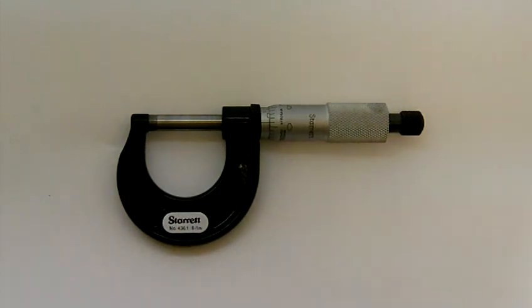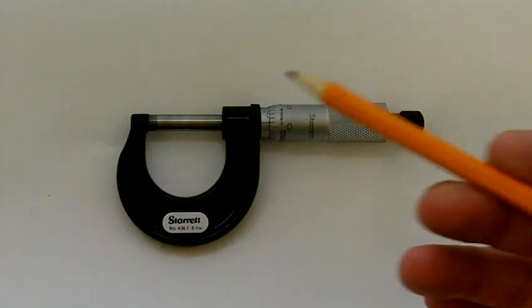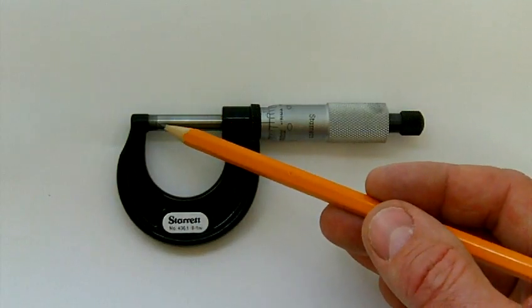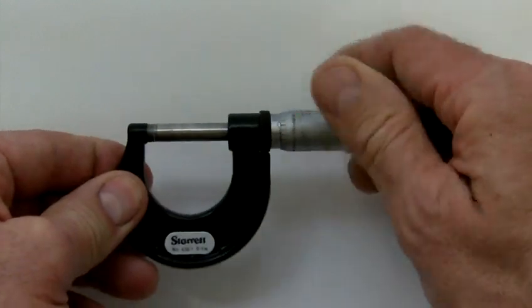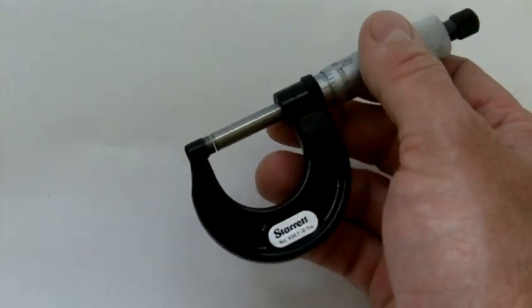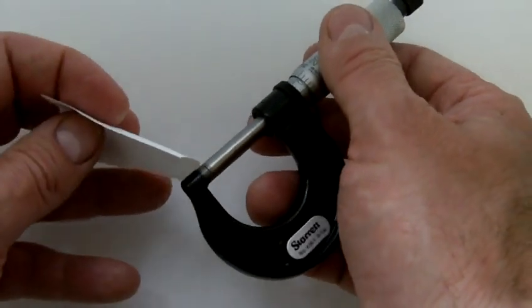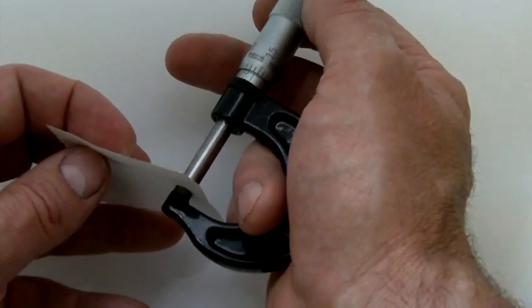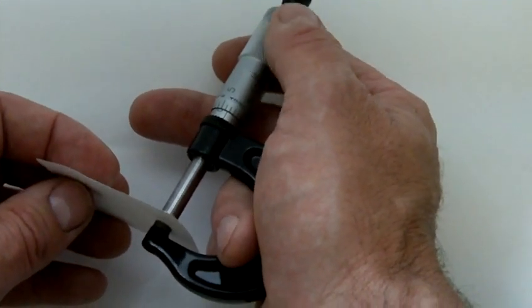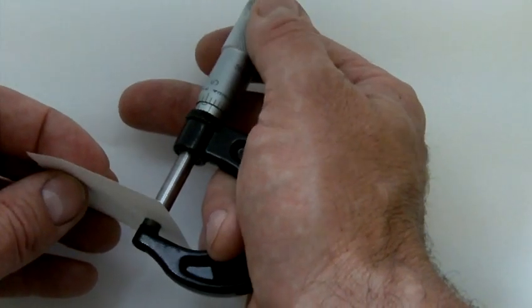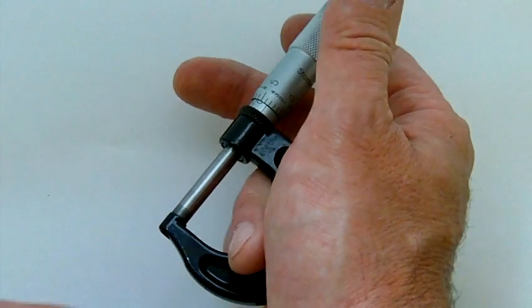The very first thing we want to do when we are checking the calibration is we want to clean the measuring points, which from the last video you know as an anvil and a spindle. So I'm going to take a piece of paper and put it between the anvil and the spindle, turn the thimble down so we get contact with the paper, and drag it off the part.